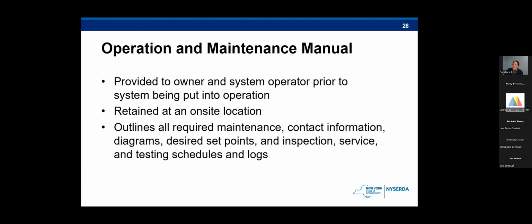And here is the operation and maintenance manual requirement. So this must be provided to both the system owner and to the system operator before the energy storage system is put into operation. The energy storage system must be operated and maintained in accordance with this manual, and a copy of the manual must be retained on site.